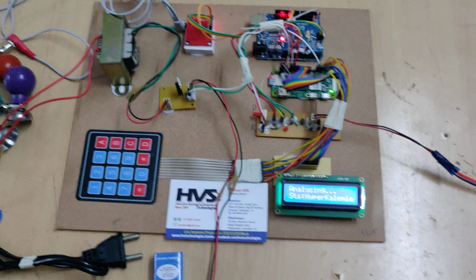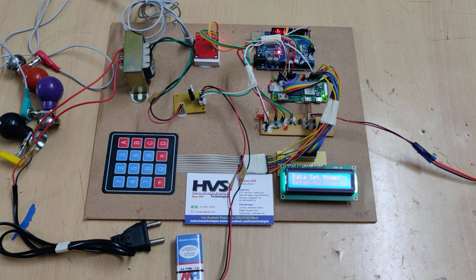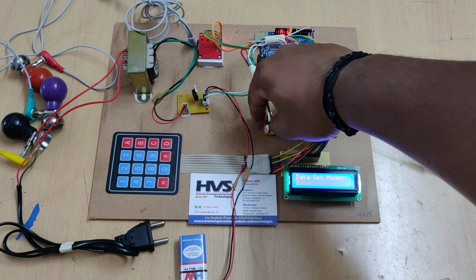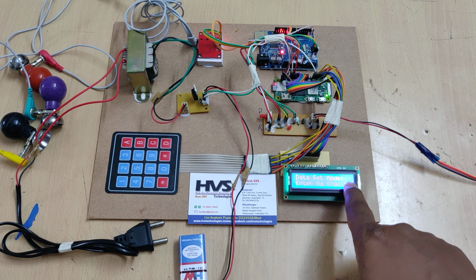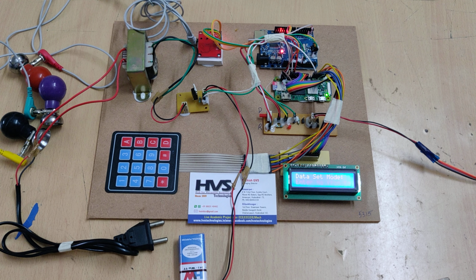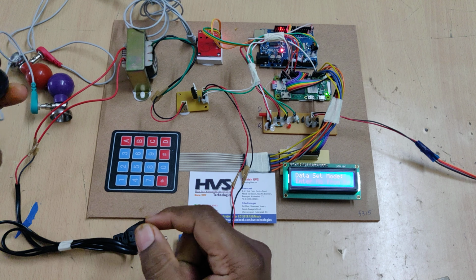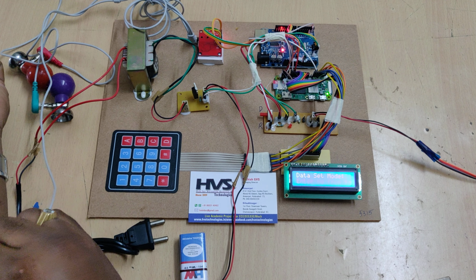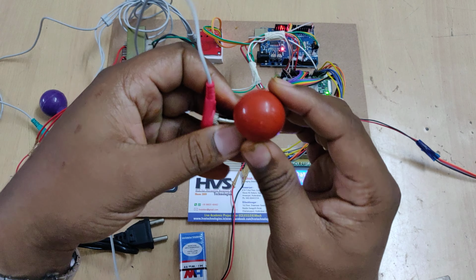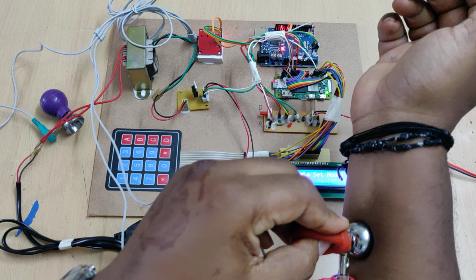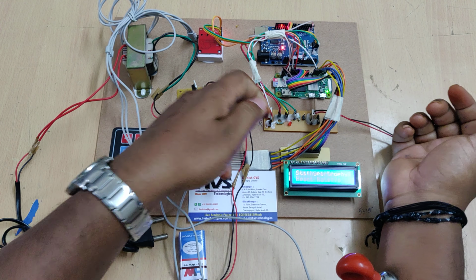Okay, and let us go with the real time mode. In that, you can change into the real time mode. So heart rate is 0. After mounting these electrodes, mount the electrodes properly on your hand, and only then can you change the mode. Otherwise it will provide abnormal data, wrong data, which leads to false disease detection. Now we are placed into the real time mode.